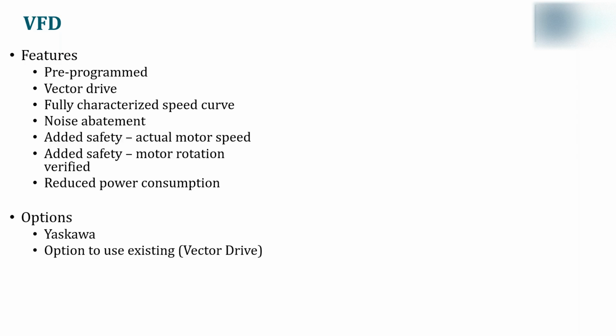Options include a Yaskawa drive, or you can use the existing drive that you already have. However, please note, make sure it's a vector drive. Why a vector drive? Well, a vector drive provides more accurate torque control of the motor. This enables much more accurate speed of the motor at lower speeds. More accuracy equals reliability and repeatability.